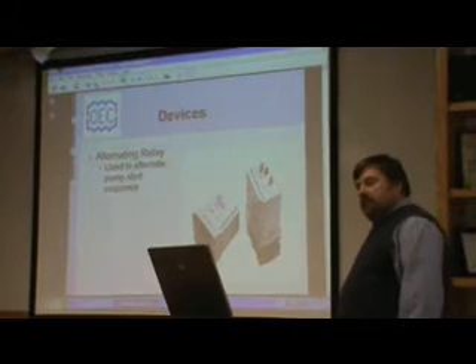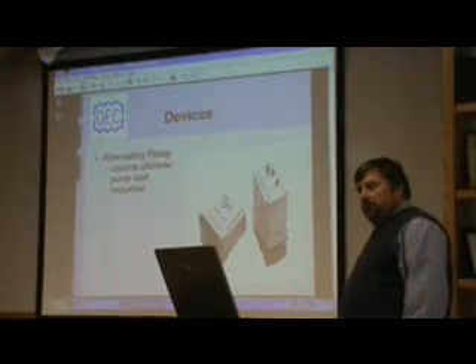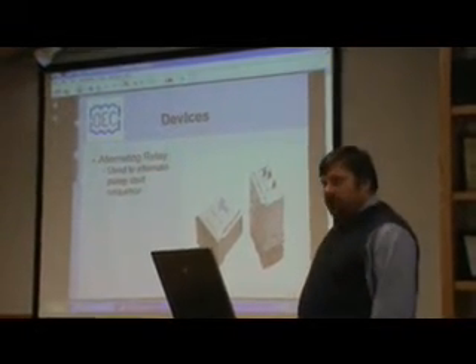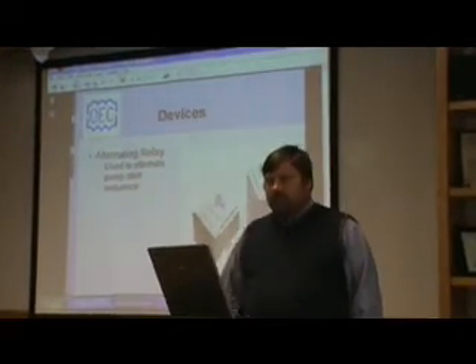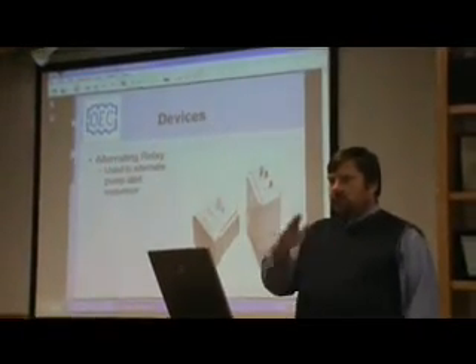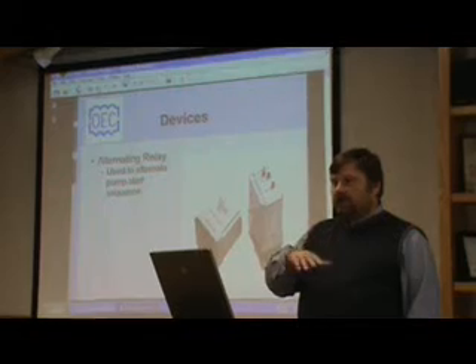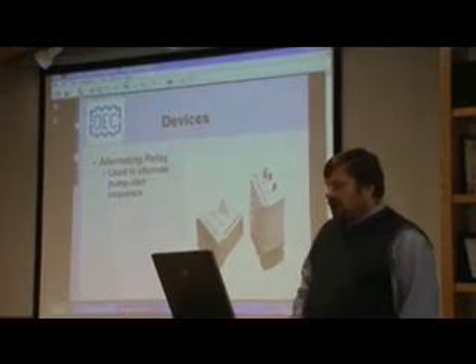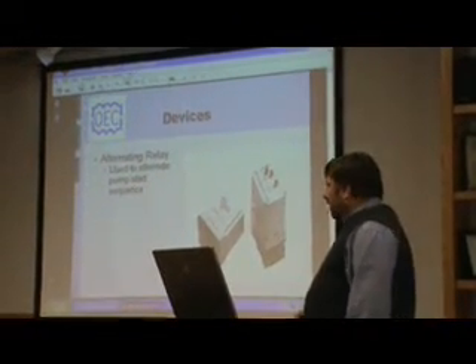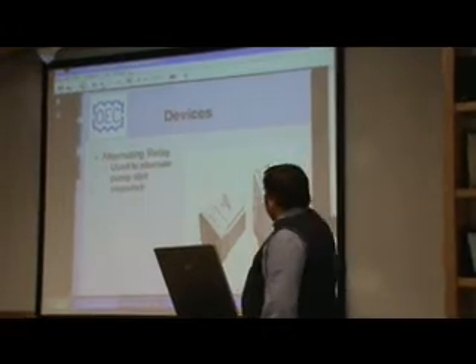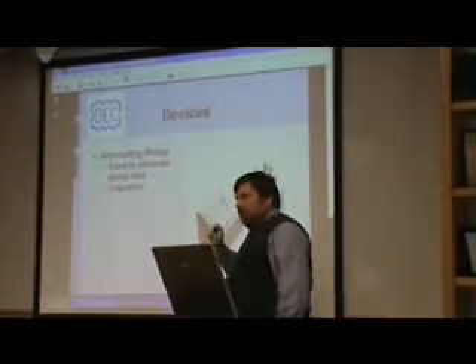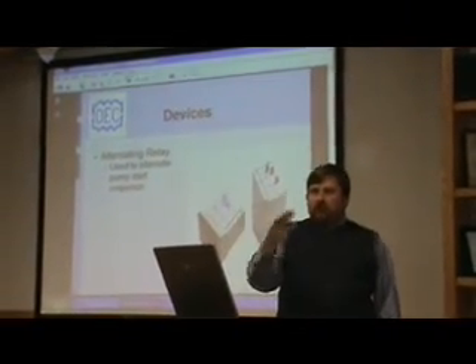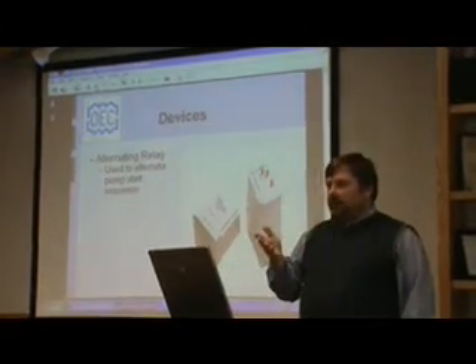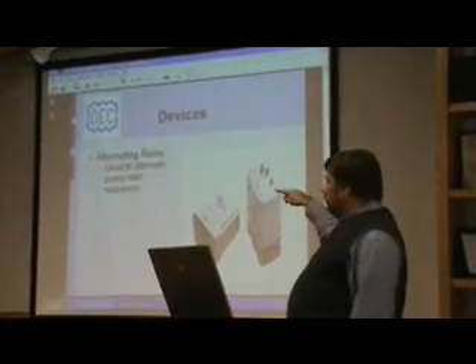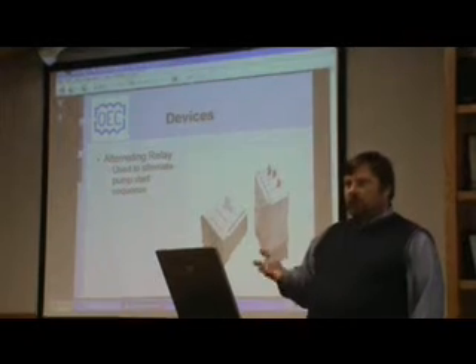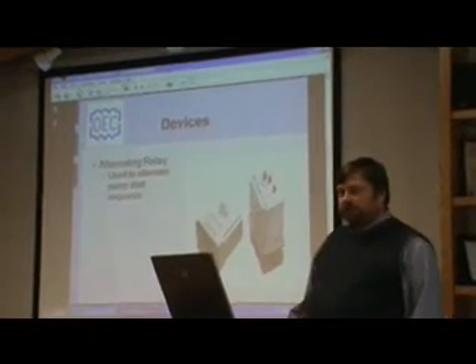fuse. The alternating relay is important if you're using a duplex station. Everybody, I'm pretty sure, is familiar with that. It just alternates the time between two pumps so that you're not running one pump all the time and the other one doesn't come on. All of the alternators that we use in our panels now have this little selector switch on the top. So if it's in the center position, it'll alternate between them. But if you have a pump go bad and you need to take pump 1 out, you can flip the switch over to pump 2, and pump 2 will always start first until you can put the other pump back in.